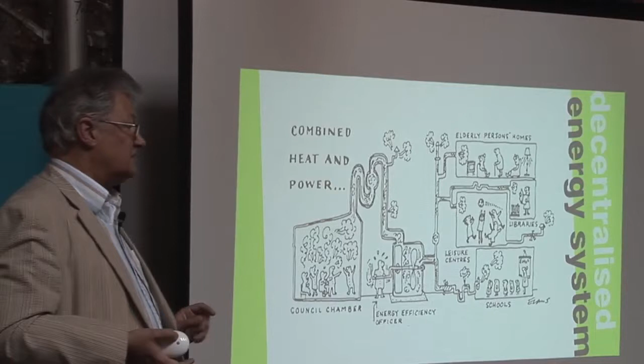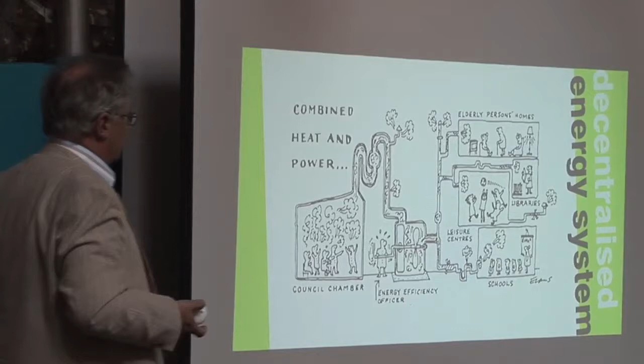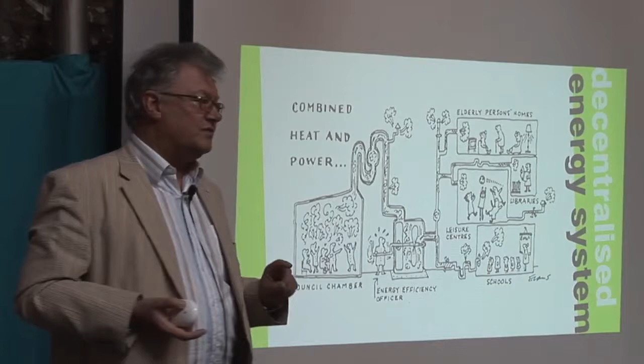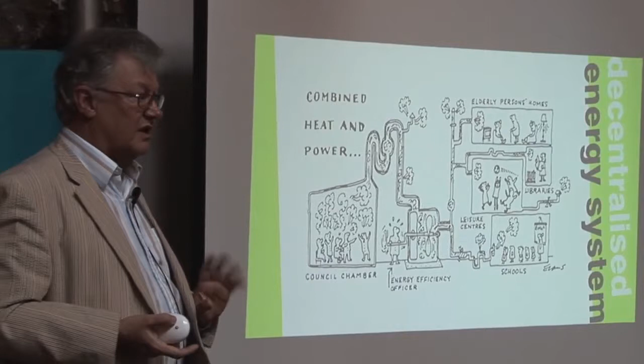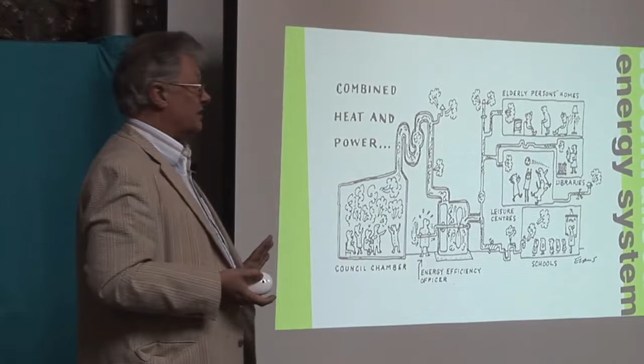Cogeneration and tri-generation are not new in Australia. There are some operating in Sydney, and I believe some in Perth as well. But they're what we call boiler-in-a-basement schemes. They just supply that building, and because of regulatory barriers, they undersize them to prevent reverse power flow going into the grid, since the economics of participating in the national electricity market makes the project uneconomic.